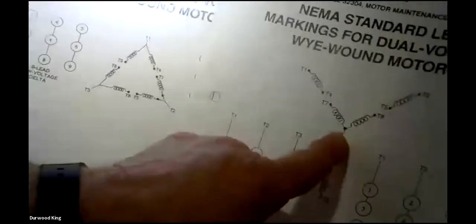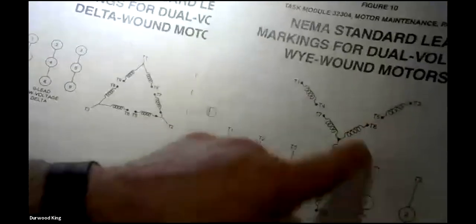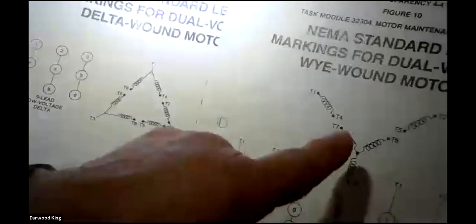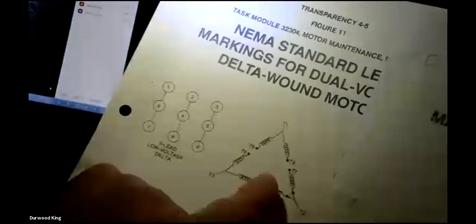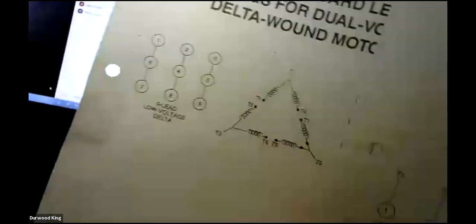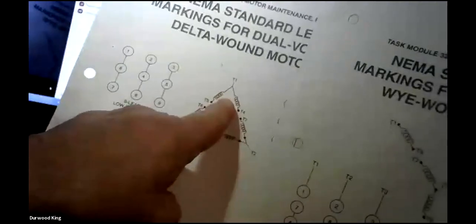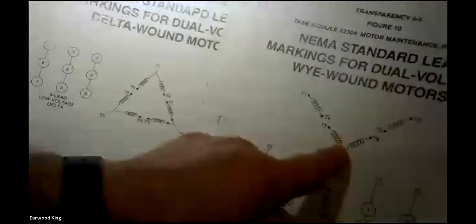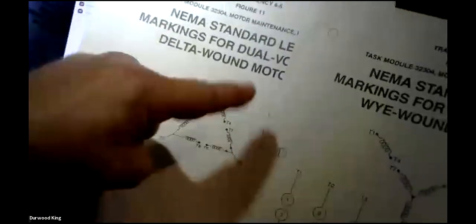And that double starter configures it like this on startup for a soft start, because that gives a soft start there. And then when you get up close to top speed, that contactor kicks out and the other one kicks in, and it changes the wiring to this for that motor externally, outside the motor. So it's called a Y start delta run. And that one motor runs Y on startup, and it switches to delta after it goes over the startup period and does a soft start. It goes into this to get higher torque.